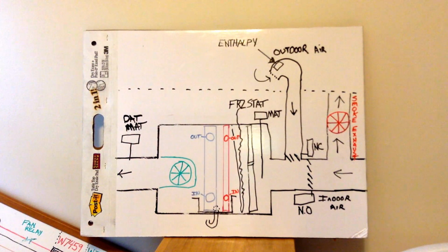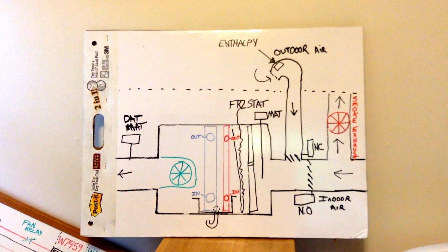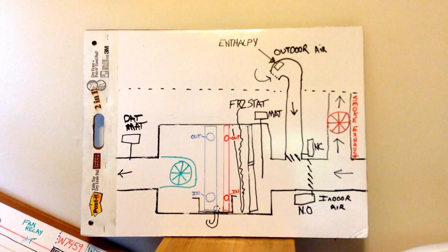here. You want to make sure that if you're leaking a little bit of 80 degree air from the store into here, it's going to kill your discharge temp. You want to make sure these shut all the way and these shut all the way. So make sure the dampers close all the way. Don't be as concerned about them opening.